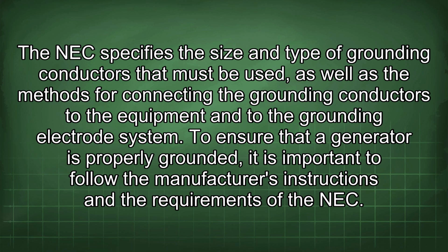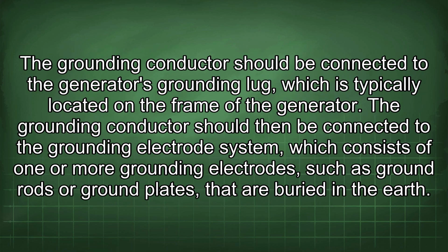To ensure that a generator is properly grounded, it is important to follow the manufacturer's instructions and the requirements of the NEC. The grounding conductor should be connected to the generator's grounding lug, which is typically located on the frame of the generator. The grounding conductor should then be connected to the grounding electrode system, which consists of one or more grounding electrodes, such as ground rods or ground plates, that are buried in the earth.